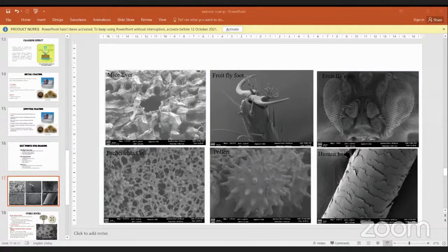Then we have the cryo scanning electron microscope also. For cryo electron microscopy, one advantage is that you don't have to process your samples. You can directly image them. Whatever your sample is, it is frozen in a preserved state with liquid nitrogen, and then transferred to the cryo preparation chamber onto the cryo stage under vacuum.